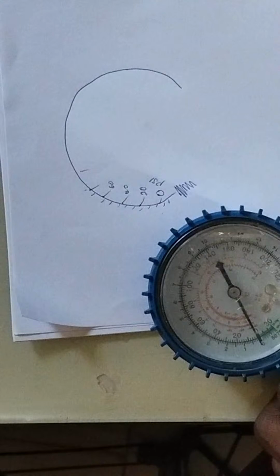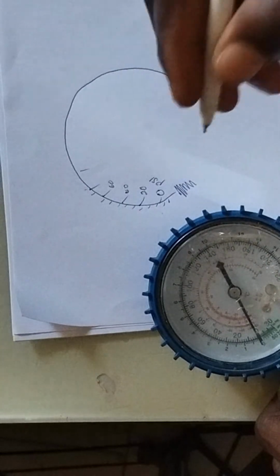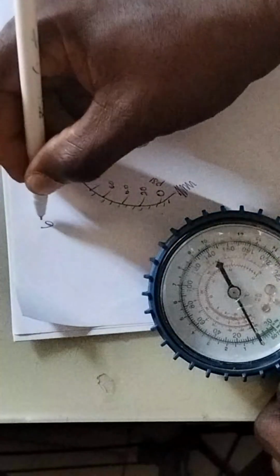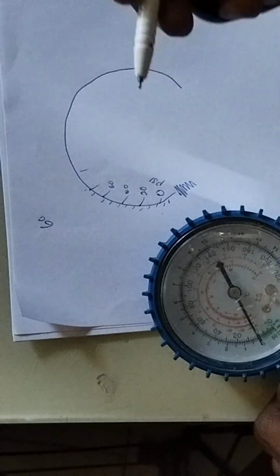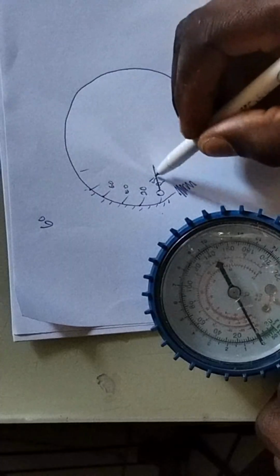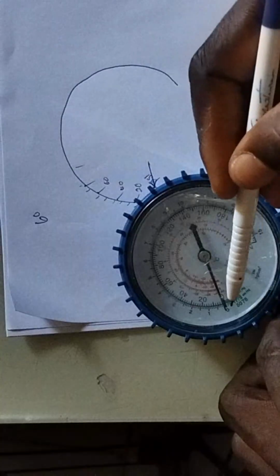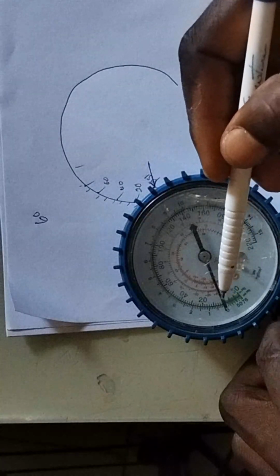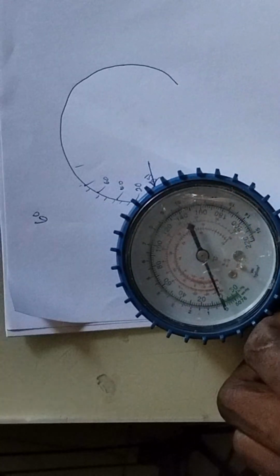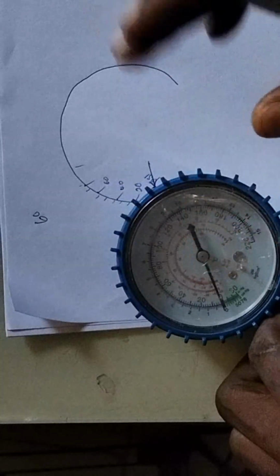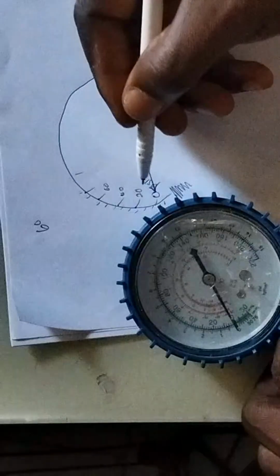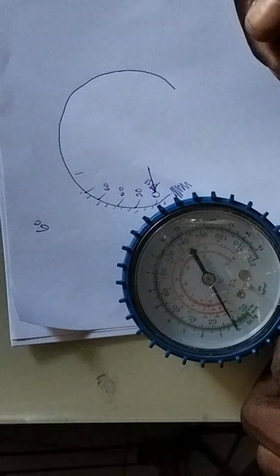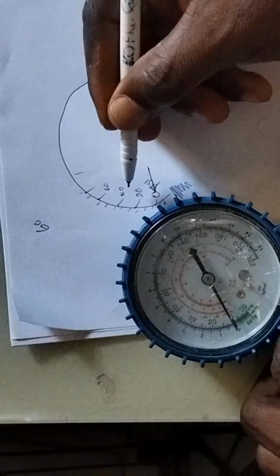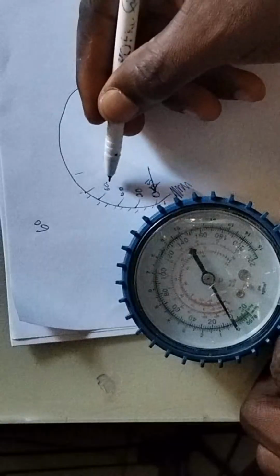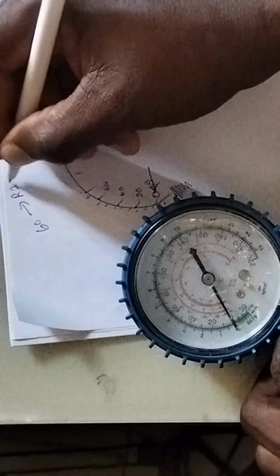Let me just use R22 refrigerant as an example. Once you charge your R22, it will start from this 0 calibration. The needle will be pointing at this zero calibration that you've just noticed here. That is what you will see while charging R22 refrigerant, or let me just say in general, it starts from 0 psi. Understand? As you gradually add the refrigerant into the system, it moves up to 20, 40, 60 psi. Now this 60 psi you see here has actually ranged out for R22 refrigerant.